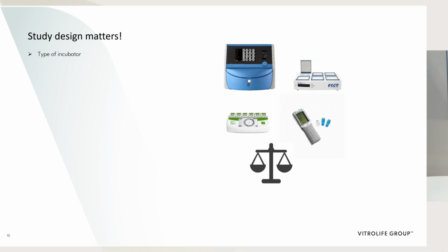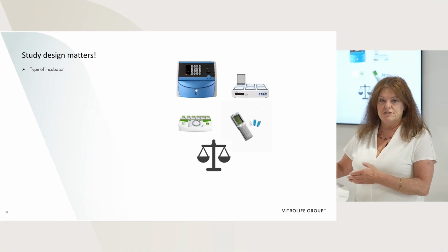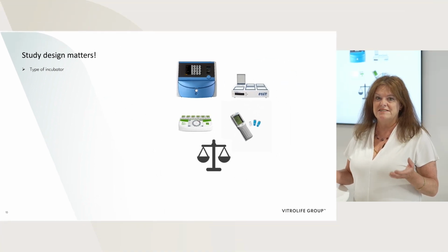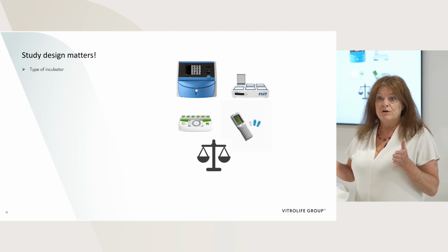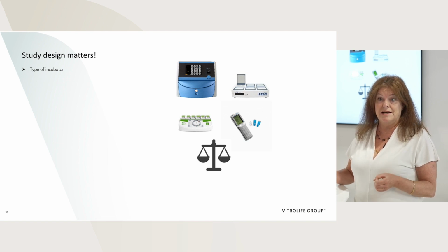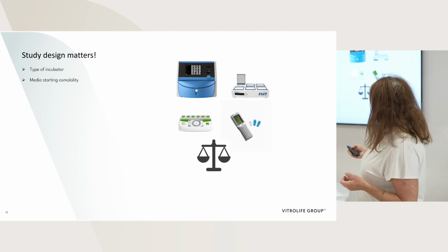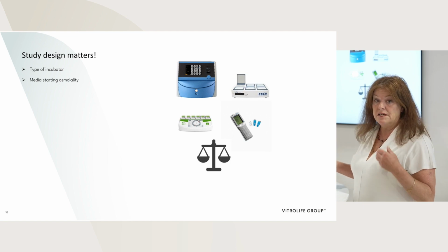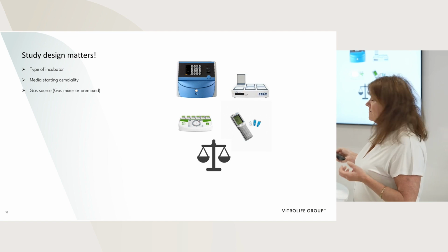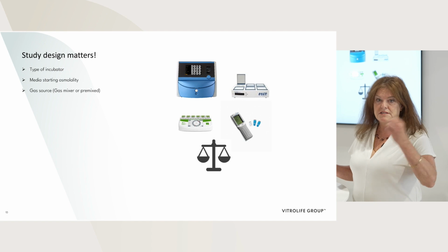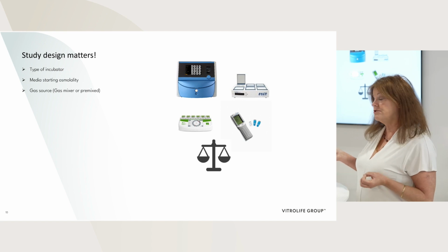Now, we've seen a lot of studies, and these studies say dry versus not dry, and they don't give details actually about how these studies were performed. If you're using an incubator with pre-mixed gas and you did or did not humidify, this makes a big difference. The starting osmolality of the media, often this is not revealed in the studies that we're seeing. The gas source, like I said, a mixer does take ambient air, so that it's not totally dry.